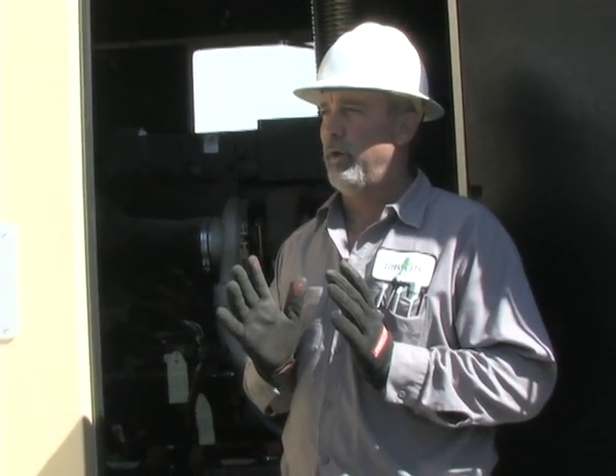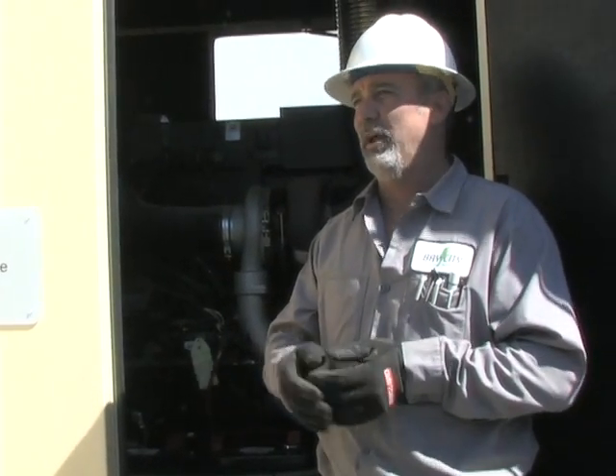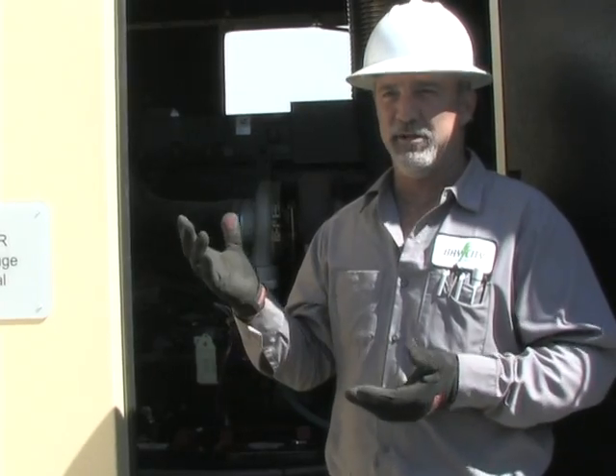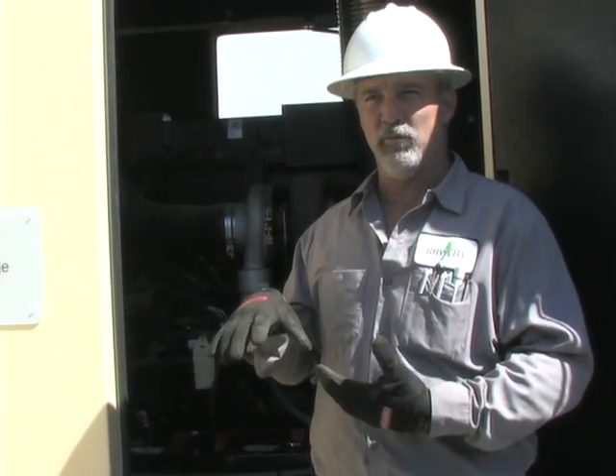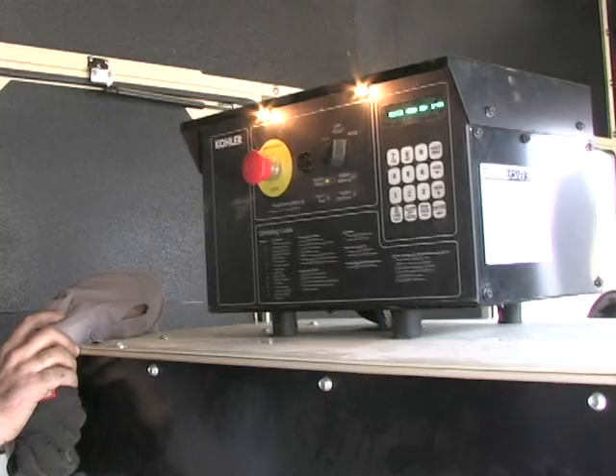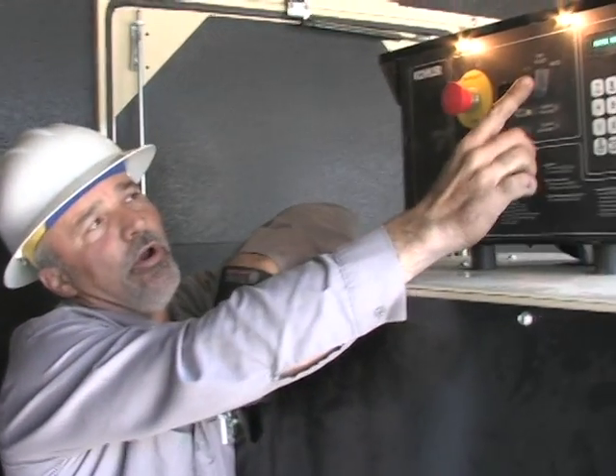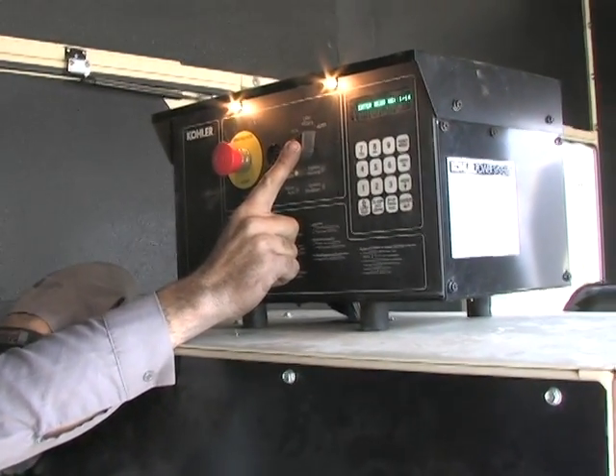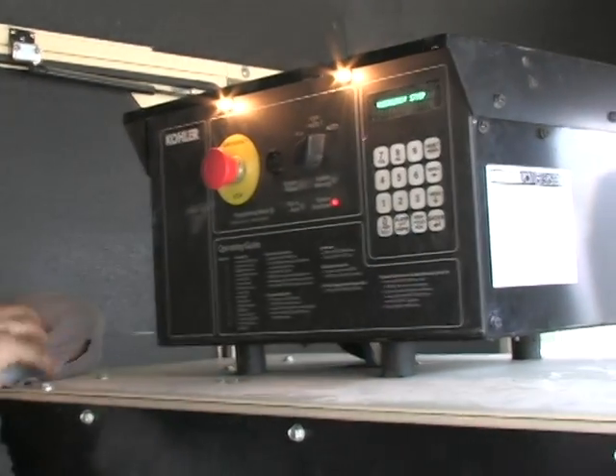Now for the good stuff — the controller. I'll show you how to start it, run it, and stop it. There is a digital panel. If there's a problem with the generator, it will come up digitally — not as a code, it will actually say what's going on. Call me on the phone, tell me what it's saying, and I'll tell you which buttons to push to rectify the situation. If that doesn't work, I'll roll out. This is your on/off switch — it's also your reset switch in case there's an emergency stop that needs to be reset.